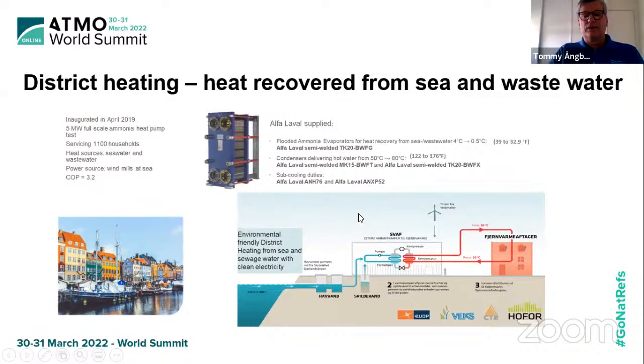And you can see there was quite a tight temperature program, because in winter we have only 4 degrees C of seawater temperature, even if we added a little wastewater, extracting heat to 0.5 degrees. And then on the hot side, district heating, circulating water from 50 to 80 degrees. And we had one semi-welded evaporator and condenser, and here we didn't have the combined subcooling. So we had an additional unit for subcooling to increase the efficiency.